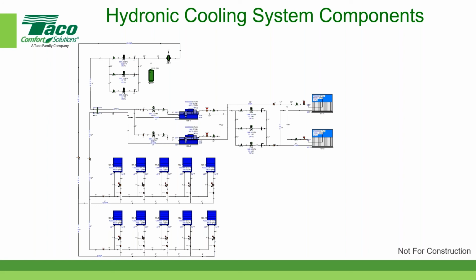Okay, yeah. So where you run piping in the building, where the insulation envelope occurs, and control of the building dew point is critical in chilled water systems design in humid areas. Even a decent insulation job can give trouble in a poorly conditioned design building. So true, right? I mean, in a conditioned space, all things being equal, let's take our headquarters building. Our dew point temperature is maintained at about 45 to 50 degrees Fahrenheit in the summertime. And if we allowed the dew point temperature to rise, not only would the building be uncomfortable, but we run the risk of components sweating where they wouldn't sweat if the dew point temperature was kept under control. So yeah, that's an important piece.